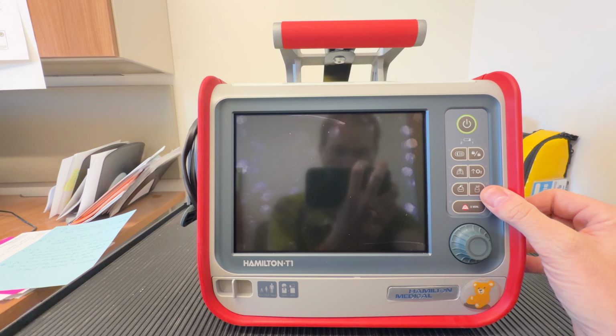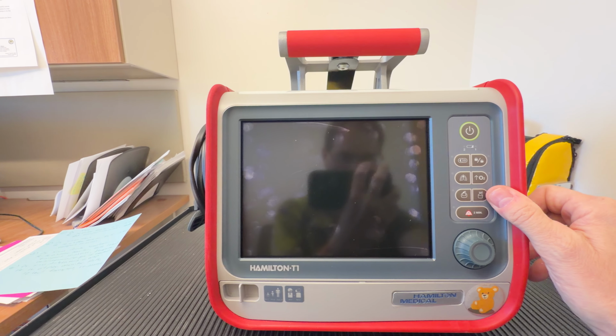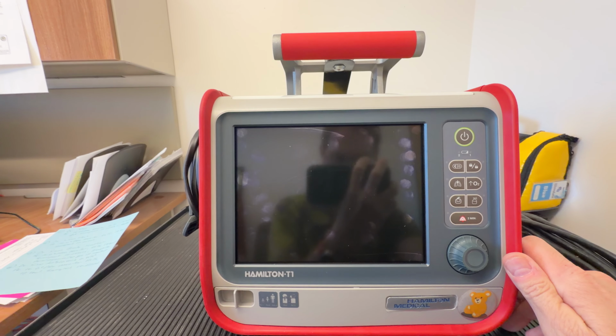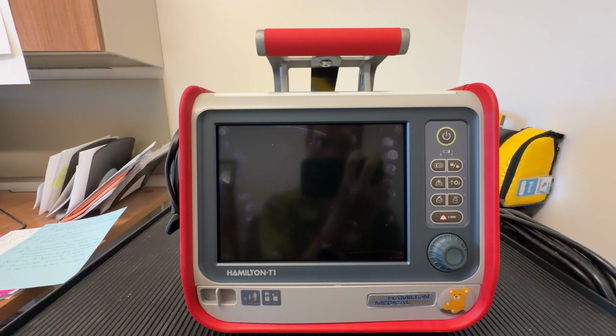This will activate a pneumatic nebulizer. I'll show you where the nebulizer port is on the ventilator here in just a little bit. And I believe you hit it and it'll put itself into nebulizer mode for about 30 minutes. It is not a continuous nebulizer like a standard handheld or low volume nebulizer, but rather it only activates the nebulizer during inspiration on the ventilator. So it's very similar to a lot of the larger hospital-based ventilator platforms.